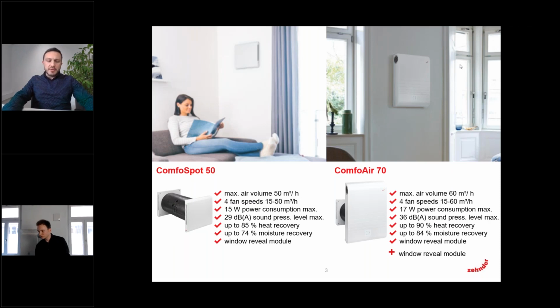Both units have around 90% of heat recovery, but also a very high percentage of moisture recovery. ComfoSpot 50 up to 74%, and the ComfoAir 70 84% of moisture recovery. Also, a very good point, we will talk a little bit later about the window reveal module.